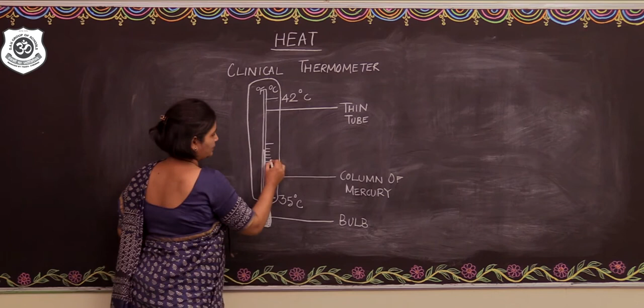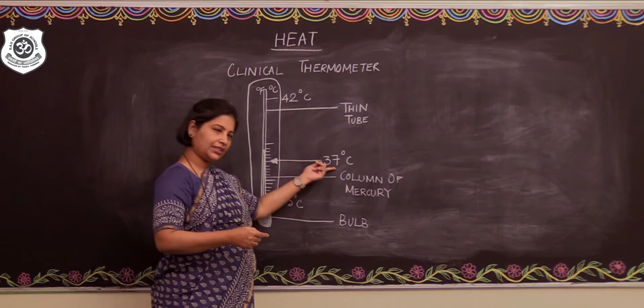Now this is encased in a glass tubing. And on this we have graduations where the temperature is expressed in either degree C or degree F. Some clinical thermometers have only the Celsius scale. Now you may be wondering what are the markings on the scale. The range of the thermometer is from 35 degrees C to 42 degrees C. Human body temperature never falls below 35 degrees C, nor does it rise above 42 degrees C, and hence these are marked as the extreme points. The lowermost point is taken as 35 and the upper point at 42 degrees C. Normally, the human body temperature is around 37 degrees C. So this is an average normal body temperature which is 37 degrees C.